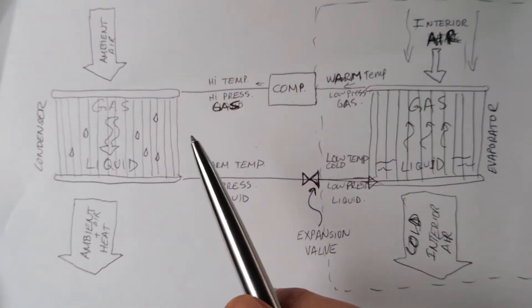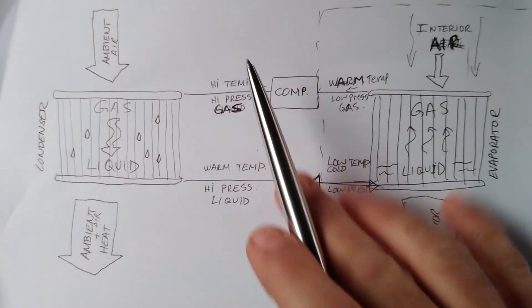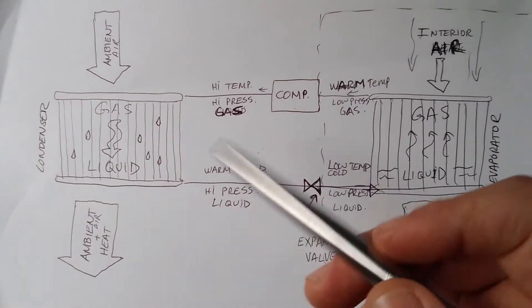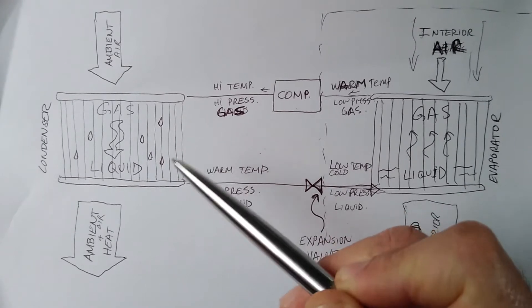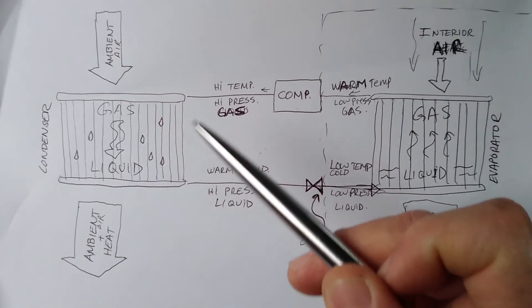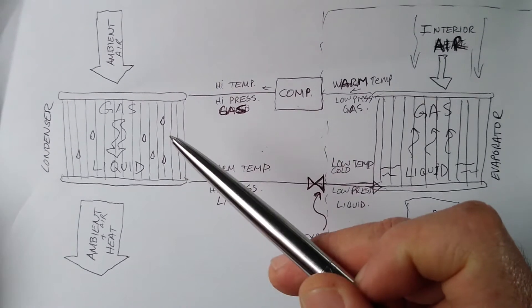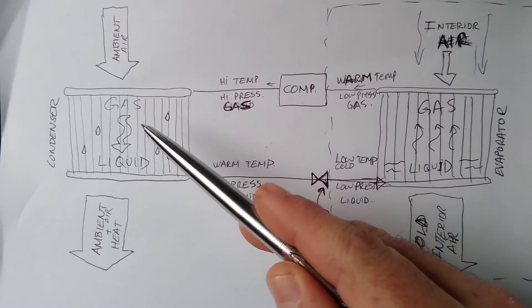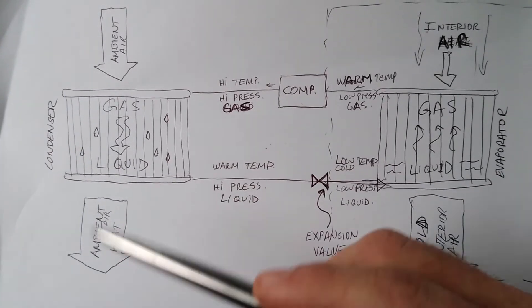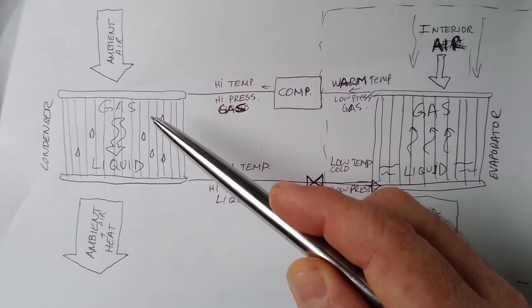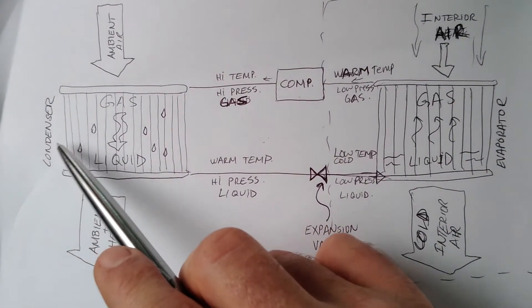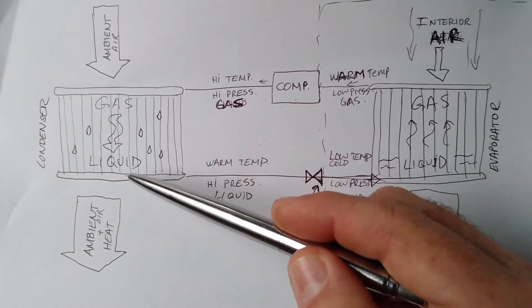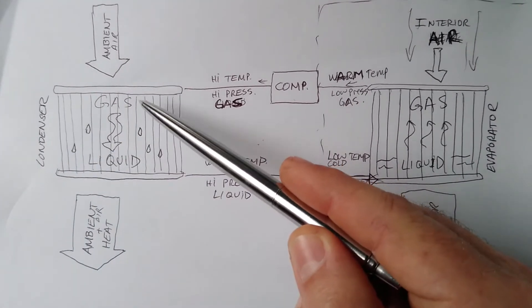This system works on the principle of latent heat — the fact that a gas, when it changes phase from gas to liquid, lets go of heat. If you start with a gas and remove enough heat from it, it will condense into a liquid. That is exactly the purpose of the condenser — to remove heat from the gas so it can condense, hence the name.